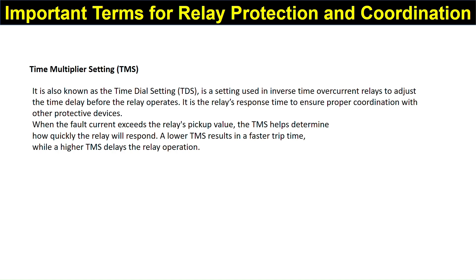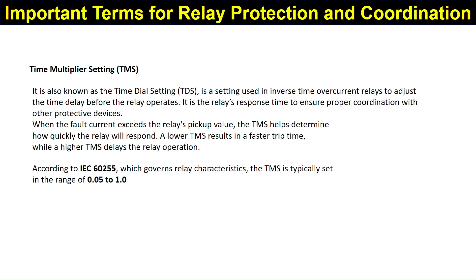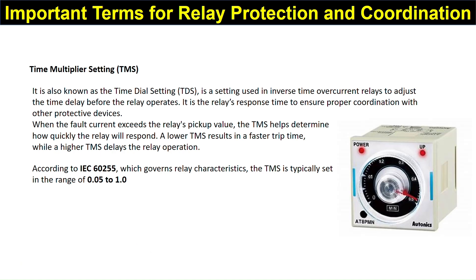A lower TMS results in a faster trip time while a higher TMS delays the relay operation. According to IEC 60255, the TMS is typically set in the range of 0.05 to 1. On the relay, you can adjust the TMS setting using the dial shown here.